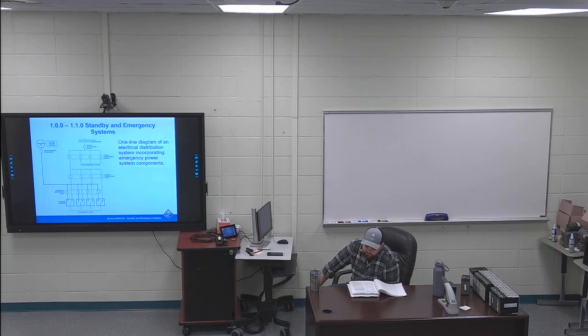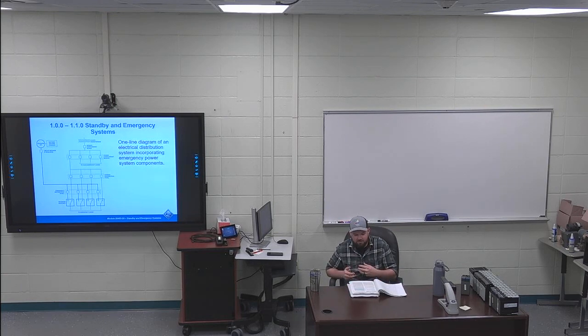Immediate next paragraph, first sentence is highlighted, separate highlight. Legally required standby systems are defined by NEC Article 701 as those systems required and classified as such by municipal, state, federal, and other codes, or by government agency having jurisdiction. So the code book says what has to have these standby electrical systems, whether that be a hospital, something that has to come back on, and how fast, and what devices have to come back on, because not everything has to come back on immediately, or at all, but stuff like the lighting and emergency systems and power, that's the stuff that must come back on.